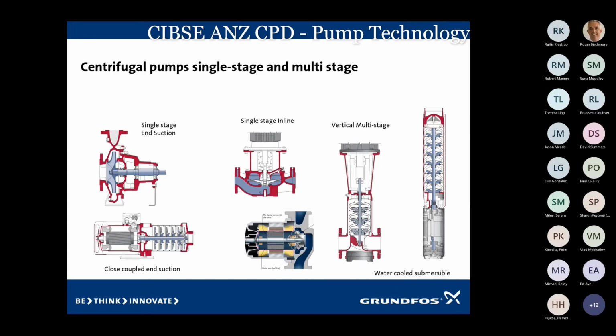If we look at the types of centrifugal pumps that we see in the bulk of our systems today, we have the single stage pumps, both end suction and inline. We also have a range of multi-stage pumps. The multi-stage pumps came out in the late 70s. Prior to that, single-stage pumps had to be generally big pumps, big base-mounted, big impellers to create a high head. Now we use multi-stage pumps, which take up a much smaller floor space and are a lot more efficient.